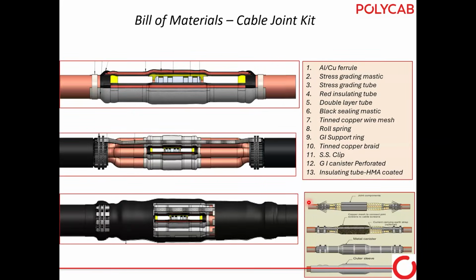So this is the final product, you can say the final joint photographs, where I have also mentioned the bill of materials here. What are the materials required to make one joint? Like aluminum or copper ferrule, stress grading mastic, yellow color stress grading mastic, stress grading tube over that, then red insulation tube, double layer tube, black sealing mastic so that water will not go in from that point. Tin copper wire mesh we use, as the copper mesh wires are there.